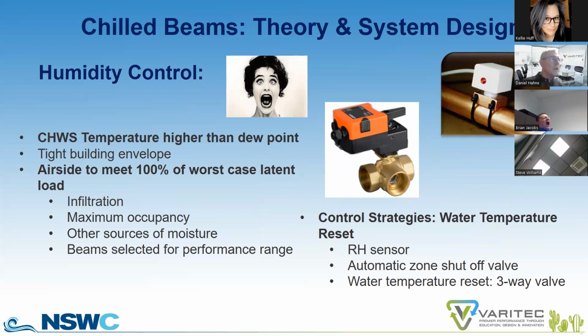So the biggest question that we're faced with is chill beams. These are condensing devices. We don't want our chill beams raining in our building, and it creates all sorts of concern. Be aware, as with any building, the latent or the humidity of a building is driven by your supply air condition. And you have to design to dew point. And by the way, ASHRAE Standard 62.1 2019 is moving from relative humidity to dew point for design conditions on humidity. And this is a big consideration.